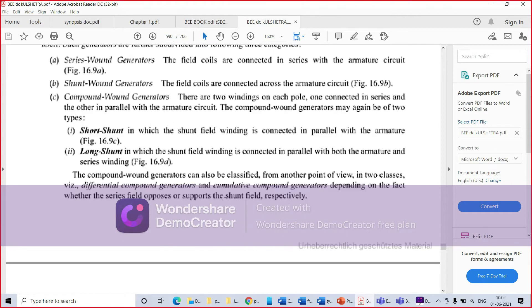You can see the diagram of your shunt wound motor — the voltage is the same. When we drew the operating characteristics of the shunt field, we took the voltage constant, so the field current and eventually the flux was constant. Similarly, here you have constant excitation — the field winding is excited through constant voltage. That is why these two motors have similar speed-armature current and torque-armature current characteristics.